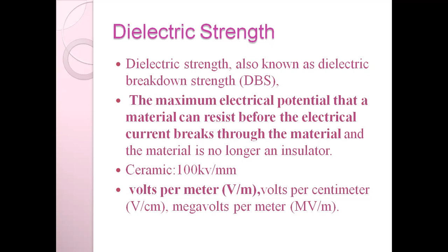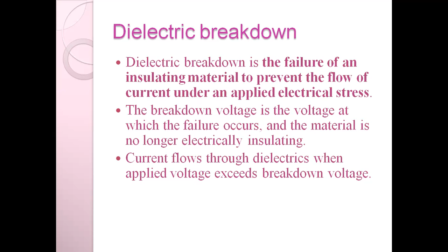Now we know what dielectric strength is, so let us know what dielectric breakdown is. Dielectric breakdown is the failure of an insulating material to prevent the flow of current under an applied electrical stress. The breakdown voltage is the voltage at which the failure occurs. In the ceramic example, if 100 is the dielectric strength, the breakdown occurs from 101. That voltage above 100 is called the breakdown voltage. Above it, the dielectric no longer remains an insulator; it starts conducting and becomes a good conductor of electricity. The material is no longer electrically insulating. So current flows through dielectrics when the applied voltage exceeds the breakdown voltage.